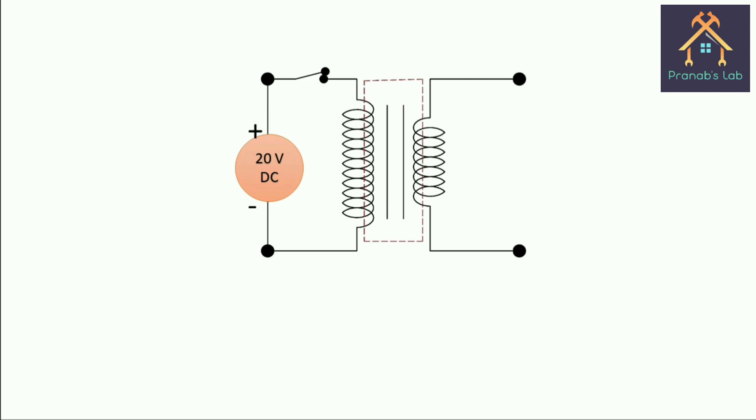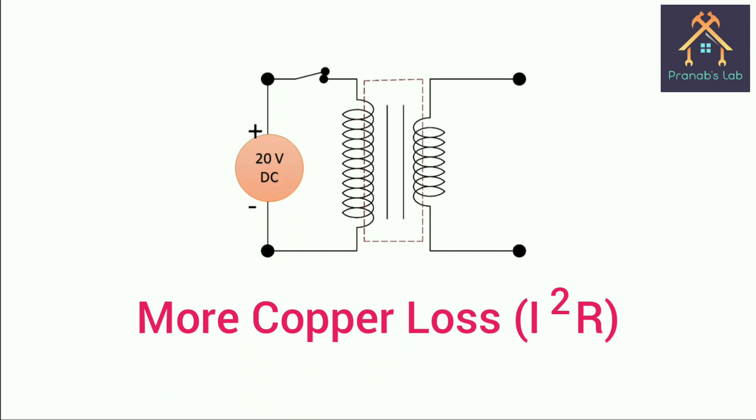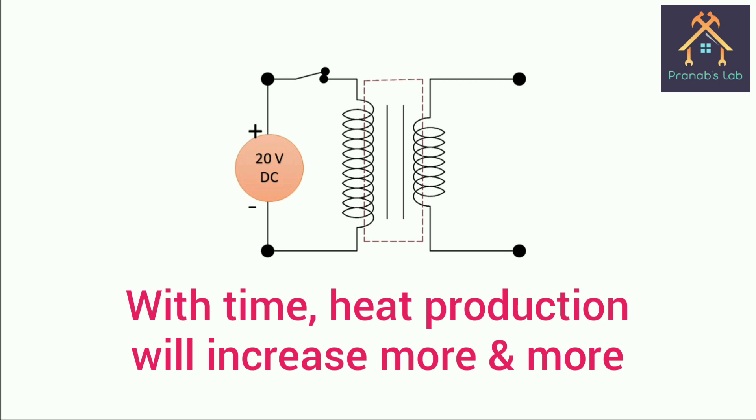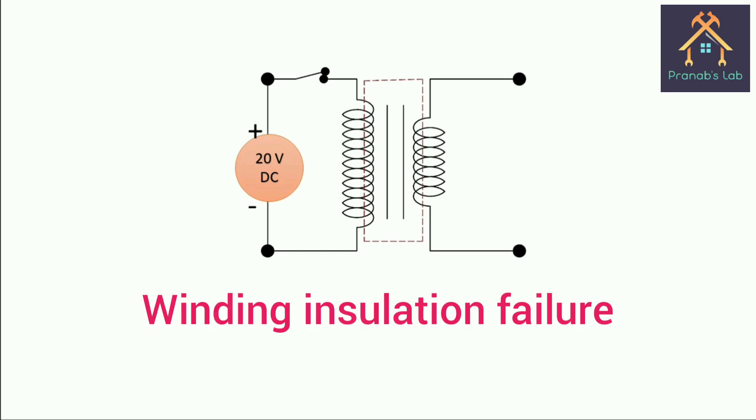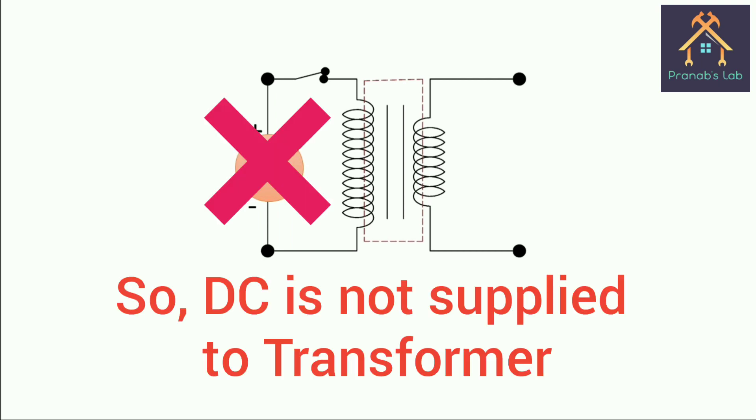In DC supply, the winding behaves like a low resistance, and when we keep the DC supply on for a few minutes, a huge amount of current flows through the winding and more copper loss occurs and the core gets heated. When the DC supply is kept for a long time, the amount of heat produced is more and more, which can be the reason for winding insulation failure and severe short circuit. To avoid this danger, the DC supply is not applied on transformers.